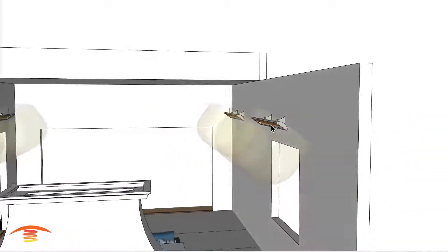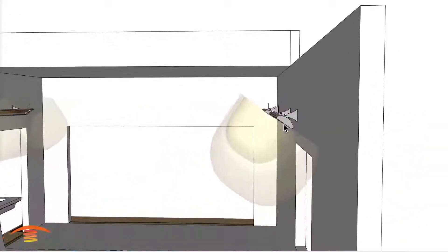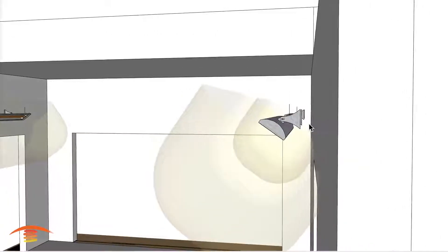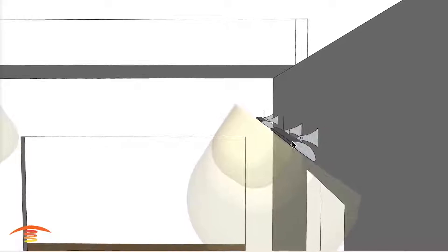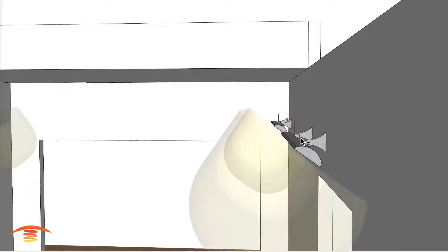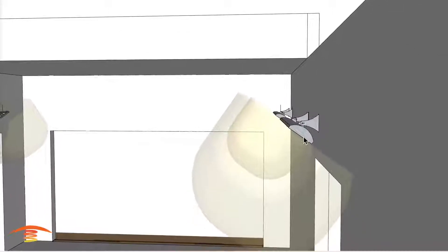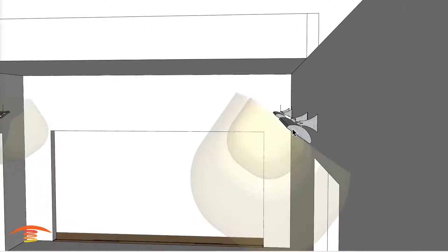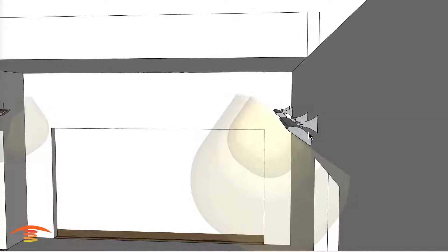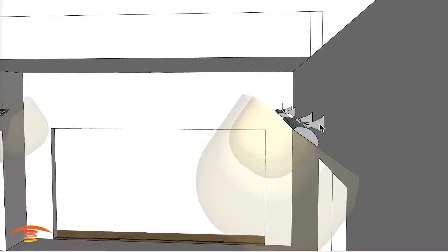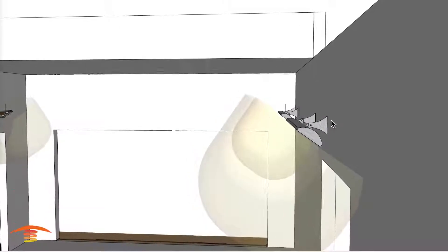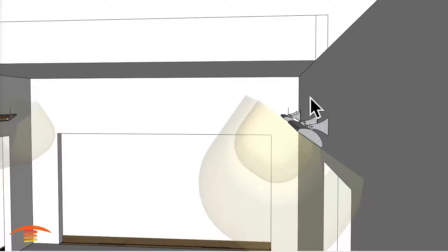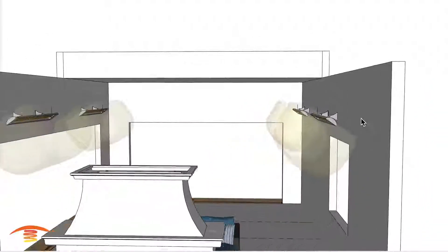And that's true with all heaters. Now, InfraTech does state that on a wall mount application, you can use up to 60 degree tilt down from straight out. So 60 degrees down and the provided wall mount is acceptable. You just cannot have anything higher on this. This is a CD model. You just can't have anything above 12 inches above the heater. So that's combustible. You need a 12 inch clearance above. So I think that's about it. And I have four of the CD 6024. These are 6,000 watt, 240 volt and 25 amps a piece. And that's true on the other units as well. There are WDs however, because they're a little bit less expensive and they provide the exact same amount of heat and you're just not going to see the finish of it. So that's why I would suggest a nicer looking unit out here where they're attached on a wall versus recessed inside of a flush mount kit.